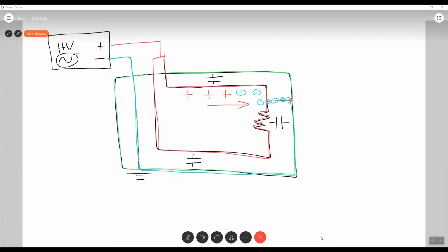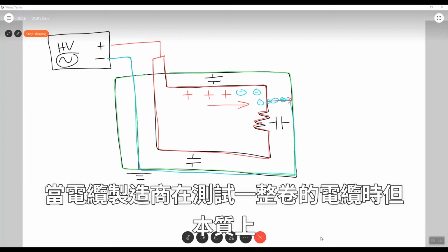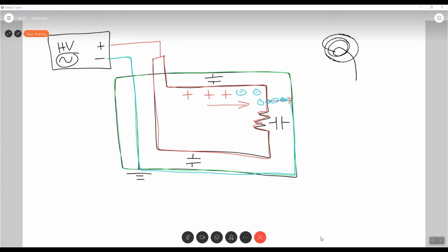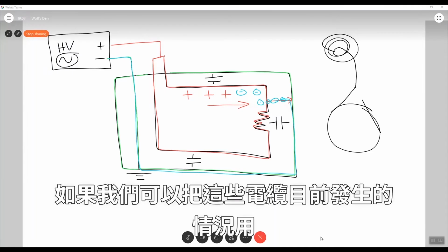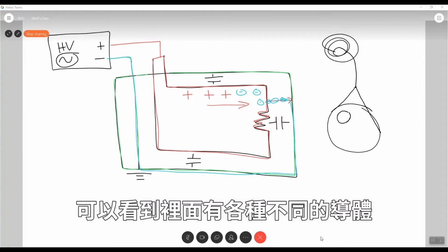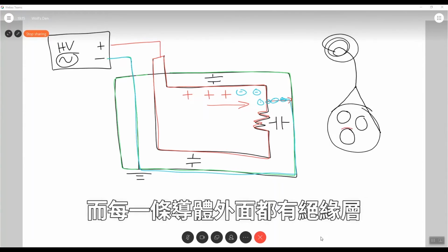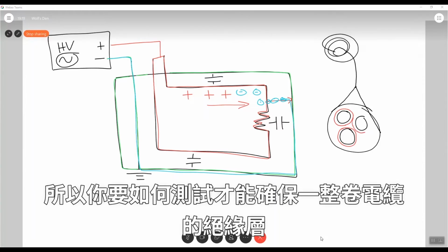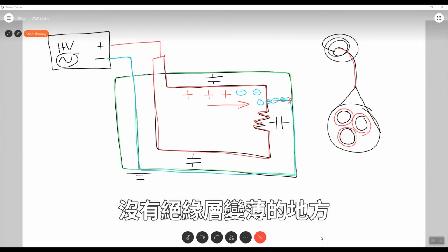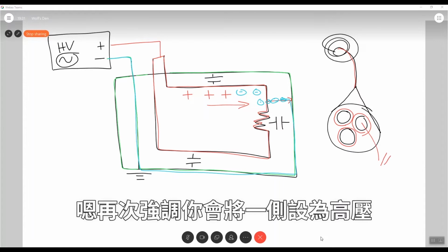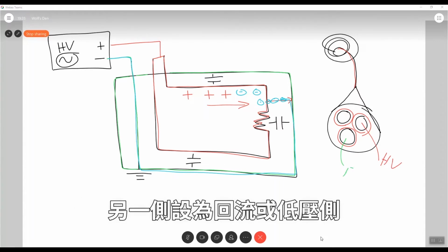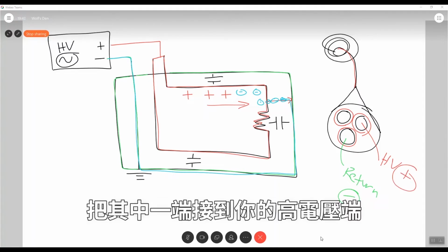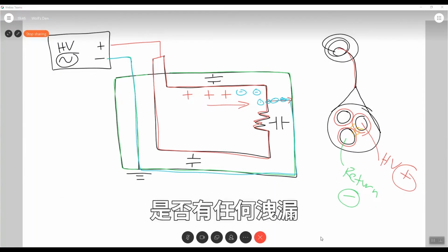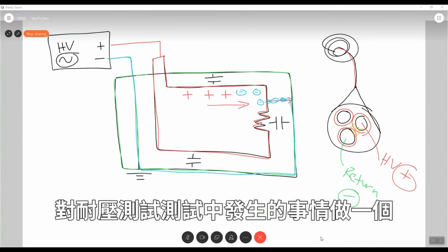That's why when manufacturers of cables test these spools of cables, in essence all they're really doing is, if we take a cross-section of what's happening, these cables have various conductors inside of them, and those conductors all have insulation around them. And so how do you test to make sure through this entire spool there's no kinks, there's no cuts, there's no places where the insulation has become weak? Well, again, you'd set one side to HV, the other one as your return, or your low side, and again, that electric field is now in between these spaces checking for any leakage.